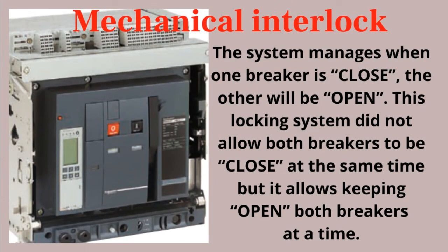The lock controls so that when one breaker is closed, the other will be open. This locking system does not allow both breakers to be closed at the same time, but it does allow both breakers to be open at the same time.